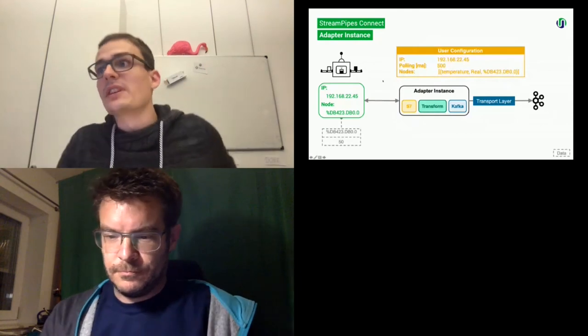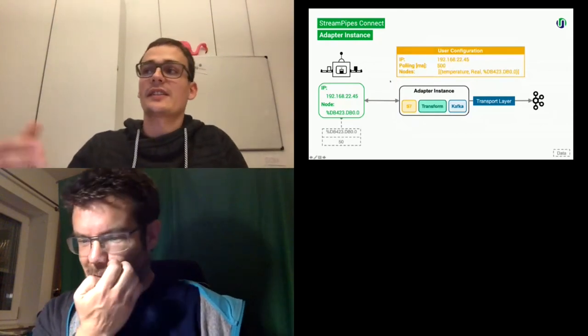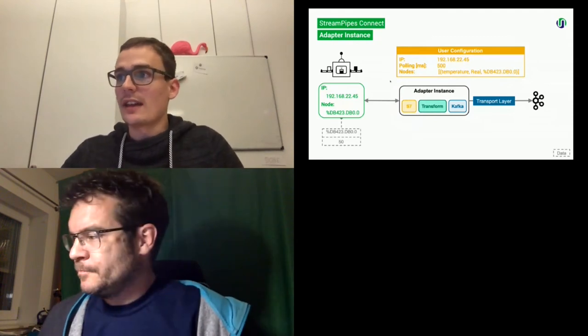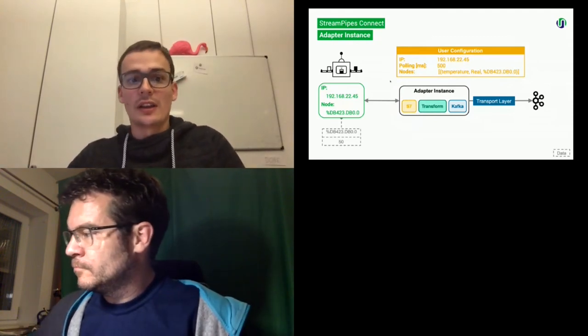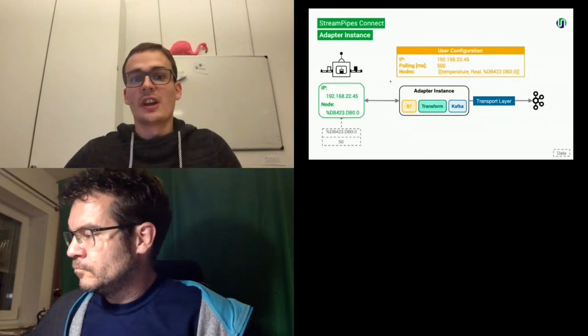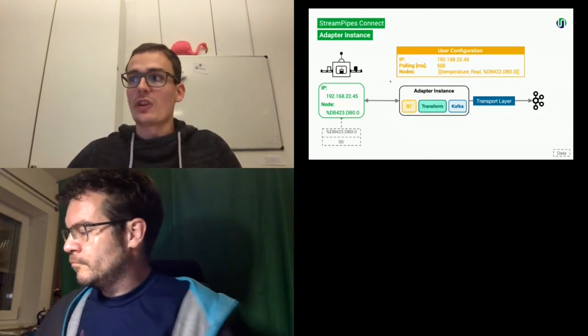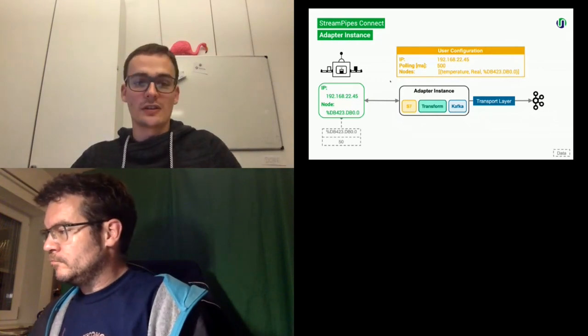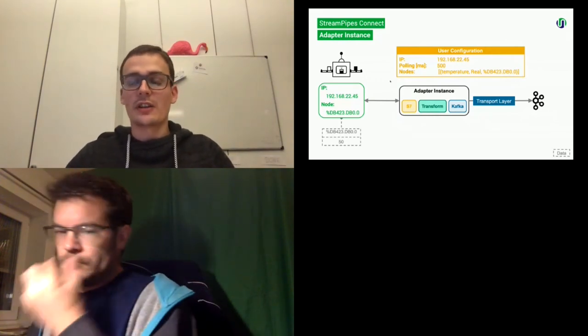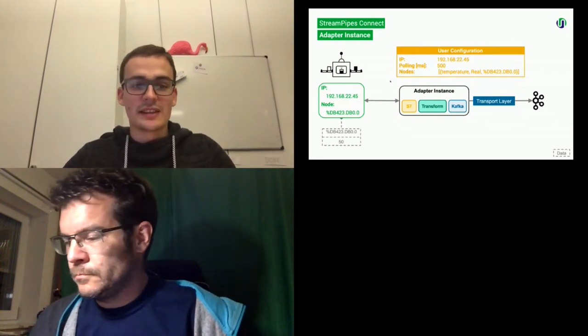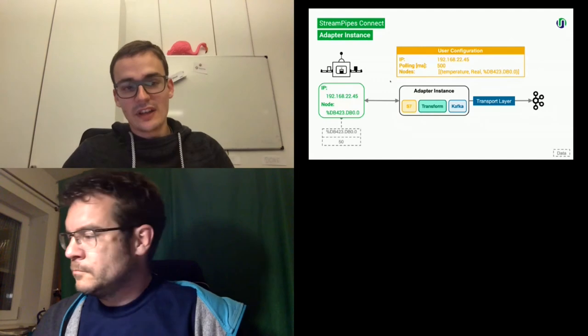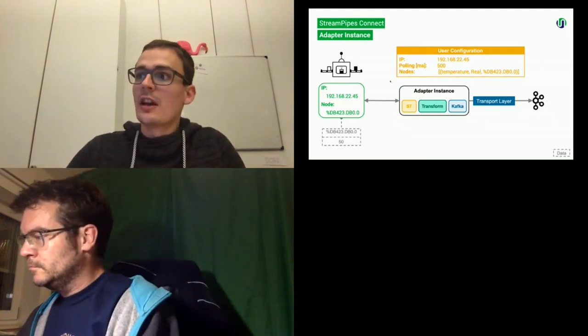Once we connect or start connecting the PLC, a user has to provide several configurations. Like you saw before in the demo, we have to enter the IP and also the polling interval and also the nodes which we want to read. So in this case, we have the node address. We provide a human readable name with temperature and also the data type. This is what is configured by the user. On the bottom left, you can see our register in the PLC, which currently has a value 50 for the temperature.